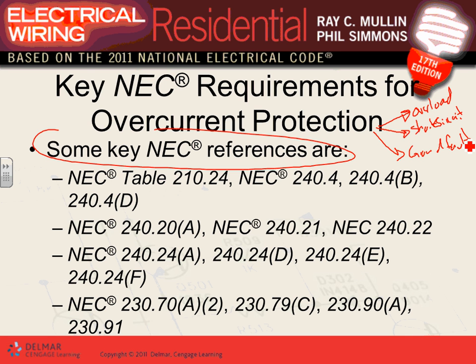Ground fault: when you have a hot or phase conductor touching a grounded object such as an equipment ground conductor or enclosure, you get a lower overcurrent than a short circuit — typically lower, but it depends on the impedance of the conduit and the contact point.